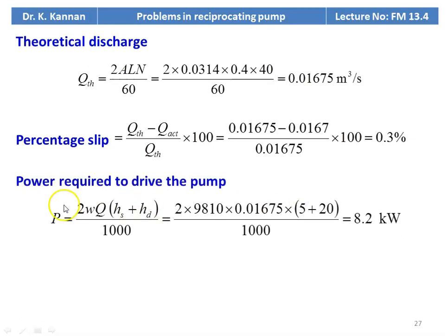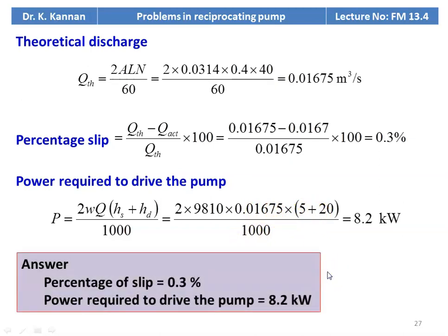The power required to drive the pump: P = 2 × W × Q × (Hs + Hd) / 1000. The factor 2 again stands for the double acting pump. Substituting: 2 × 9810 × 0.01675 × (5 + 20) / 1000 = 8.2 kilowatts. The answers: percentage of slip = 0.3%, power required to drive the pump = 8.2 kilowatt.